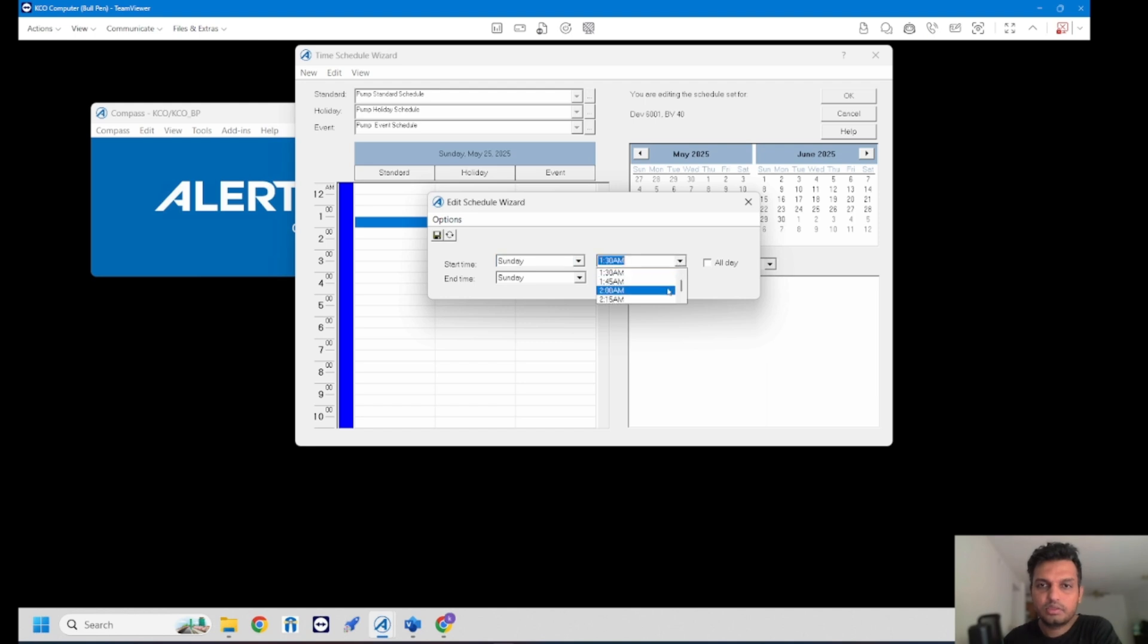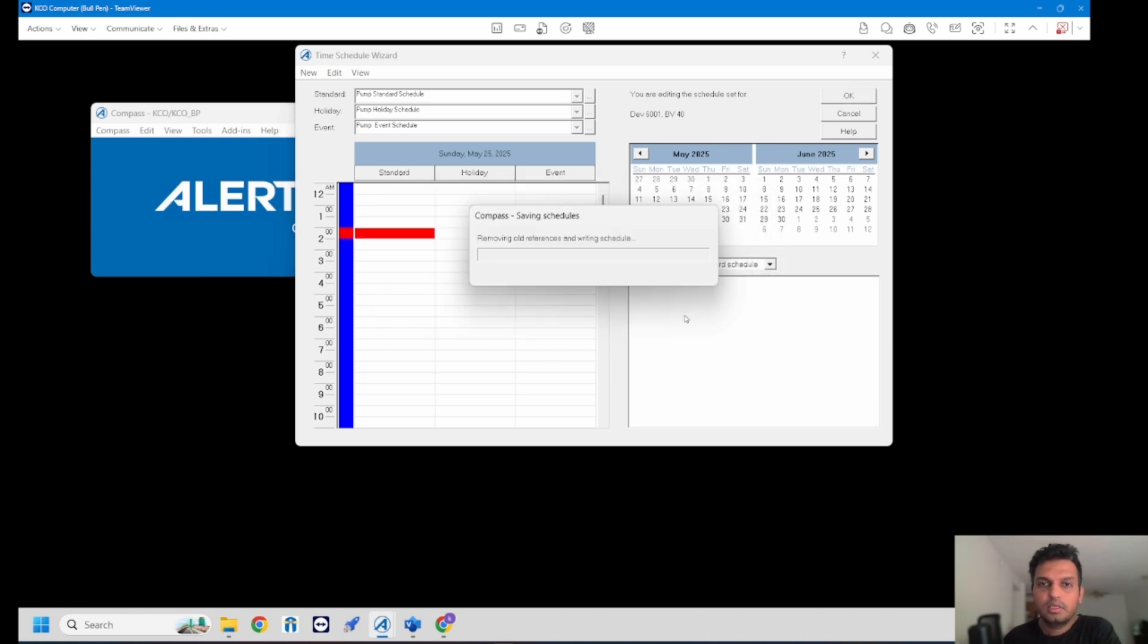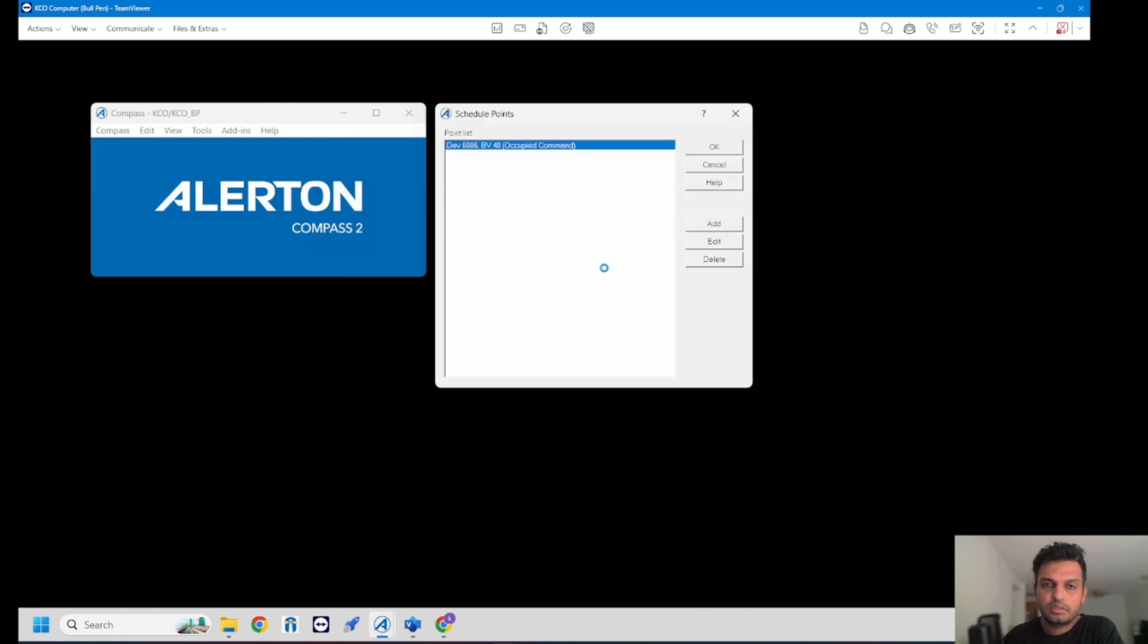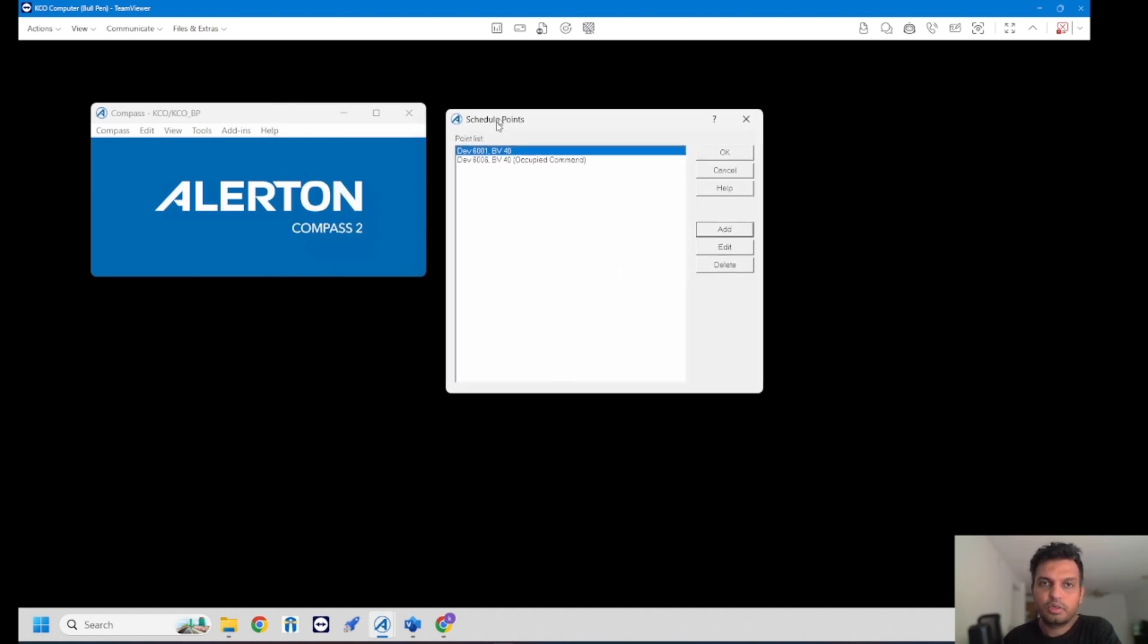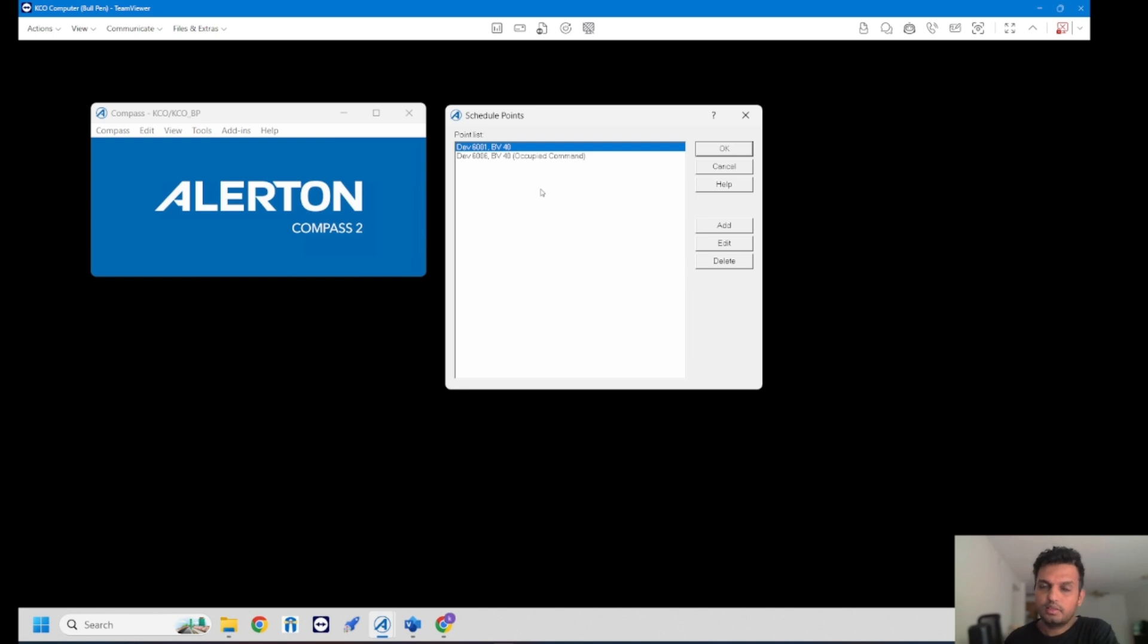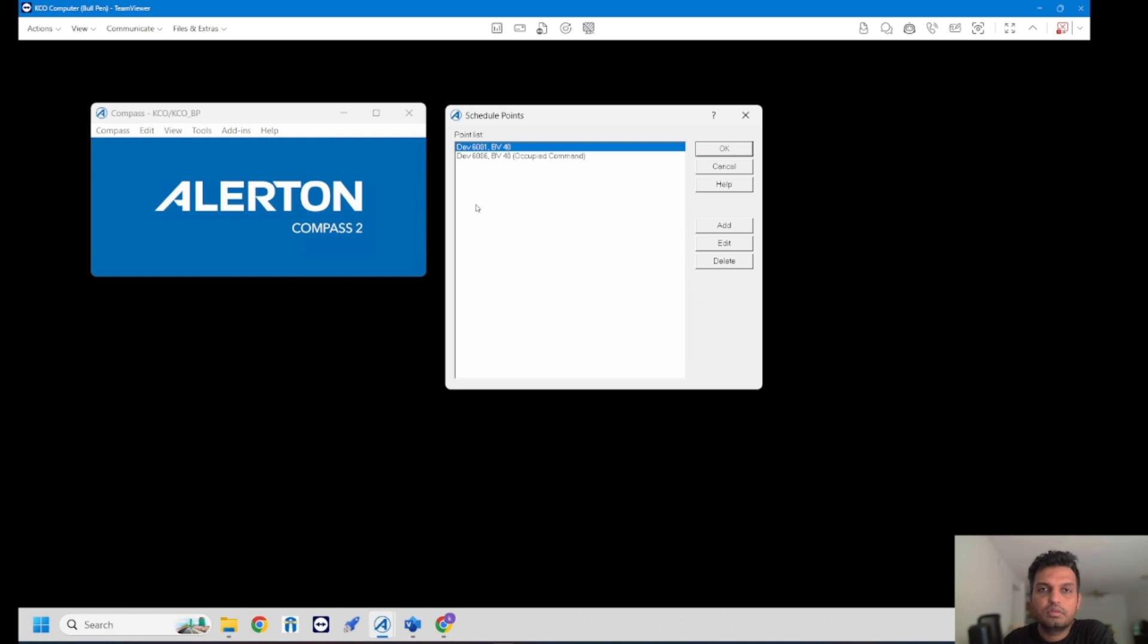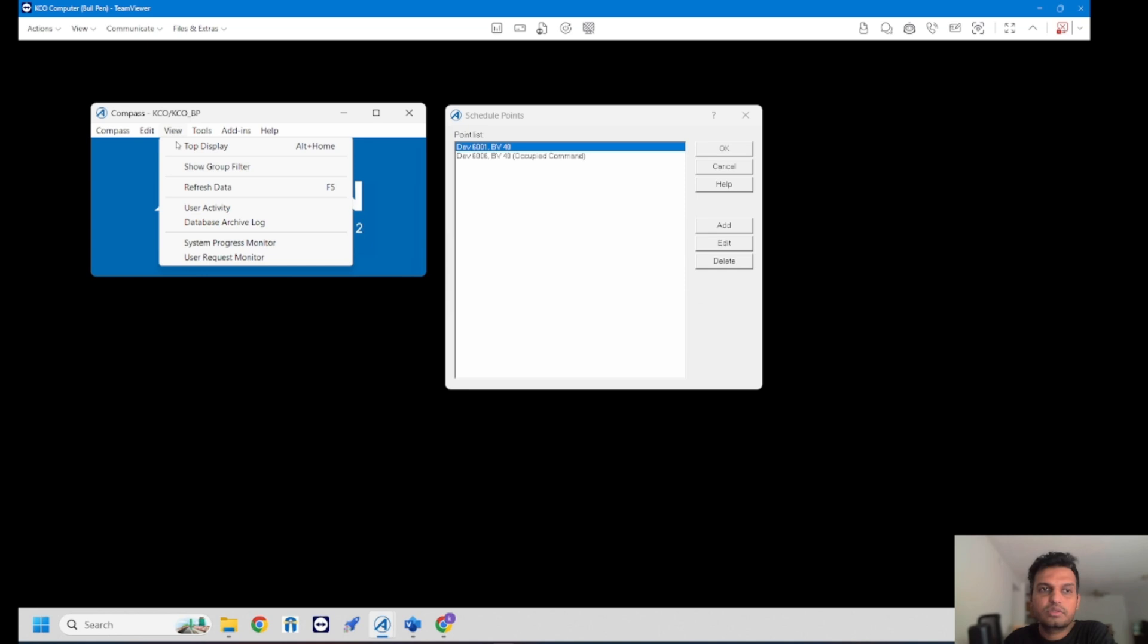I want them to be on between let's say 2 AM to 2:30 AM. Then hit save and click OK. Once you do this the schedule will be created and your schedule point list will be updated. Now you can see there's a missing naming convention, so make sure to have a proper description while downloading the DDC. Once you create the schedule you will see the proper schedule name under point schedule.